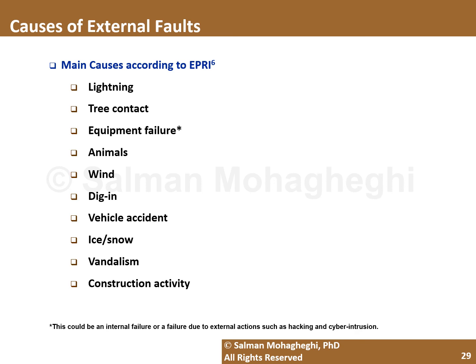Now, when it comes to external faults, there are a lot of causes for them. This could be lightning, could be contact with trees, could be the internal or external failure of an equipment, could be animals, wind leading to conductor galloping, could be digging if, for example, you're doing construction and you hit an underground cable, vehicle accident to overhead line poles, that's another cause. Ice and snow accumulation could actually lead to two things. So if you have these overhead lines and you have ice accumulation here, the line will get heavier and will sag.